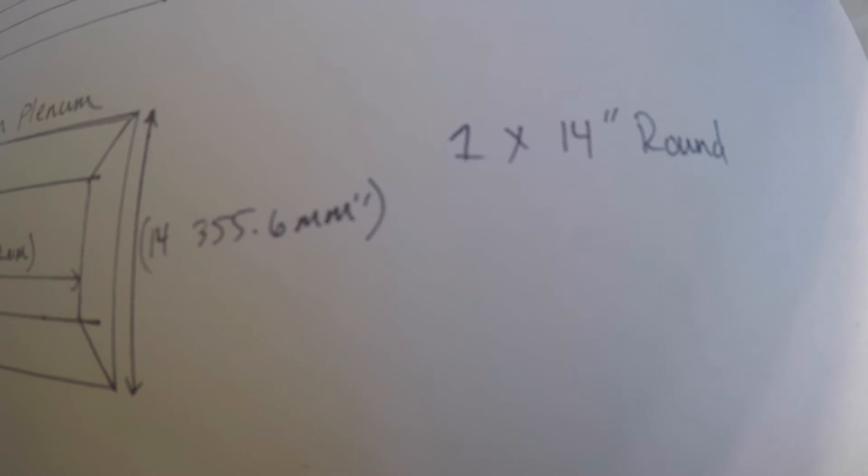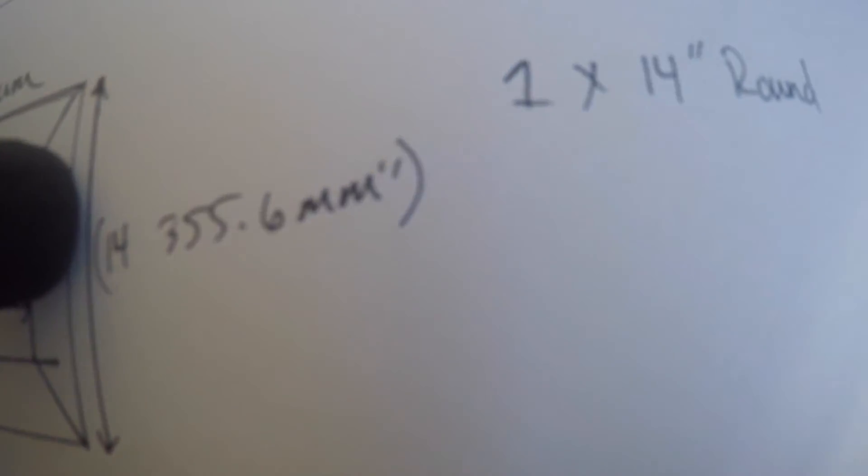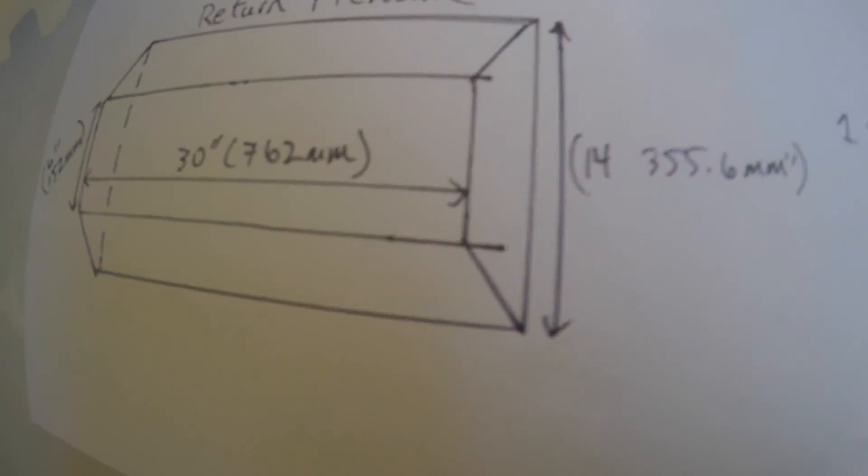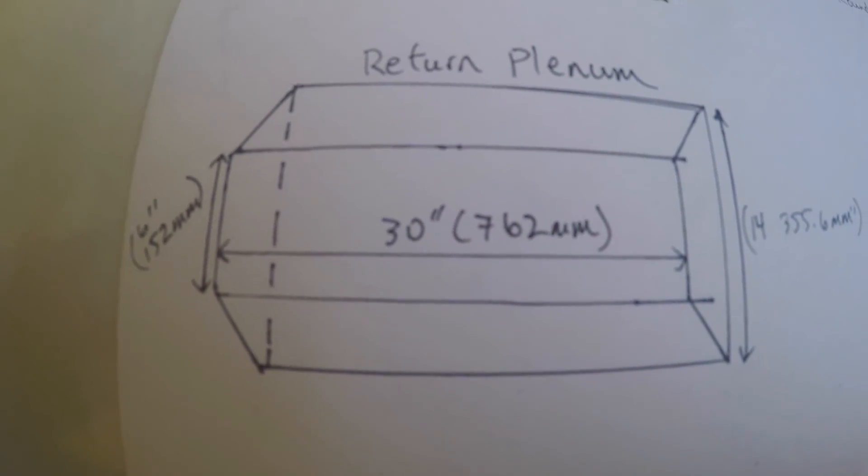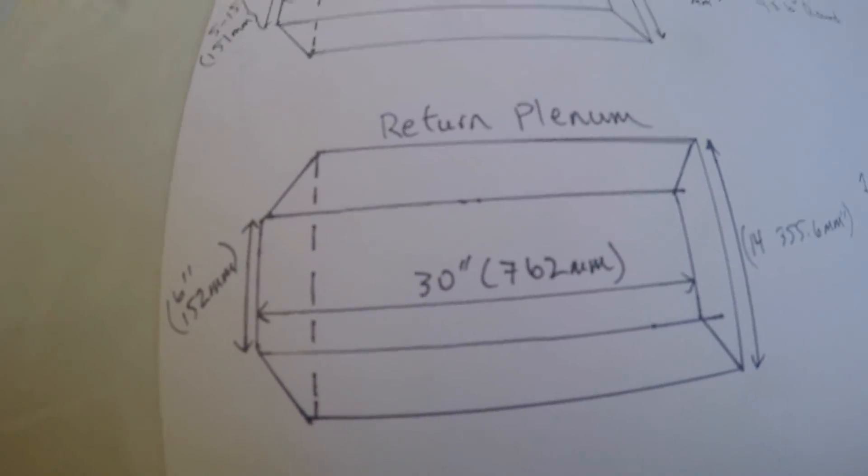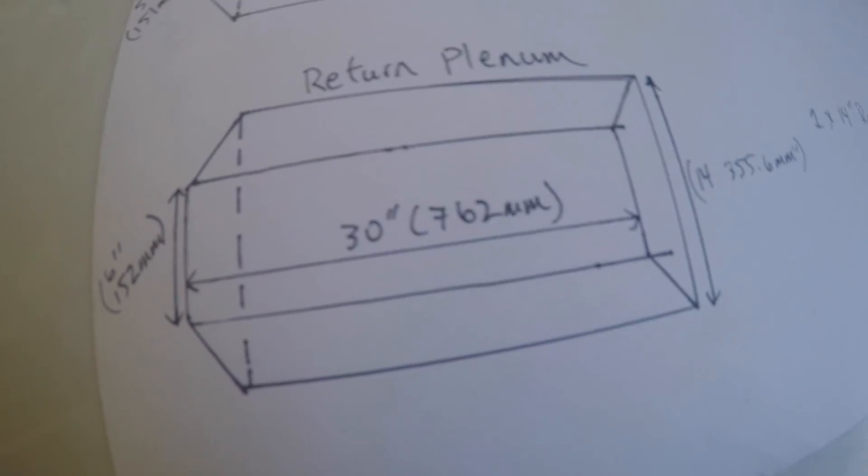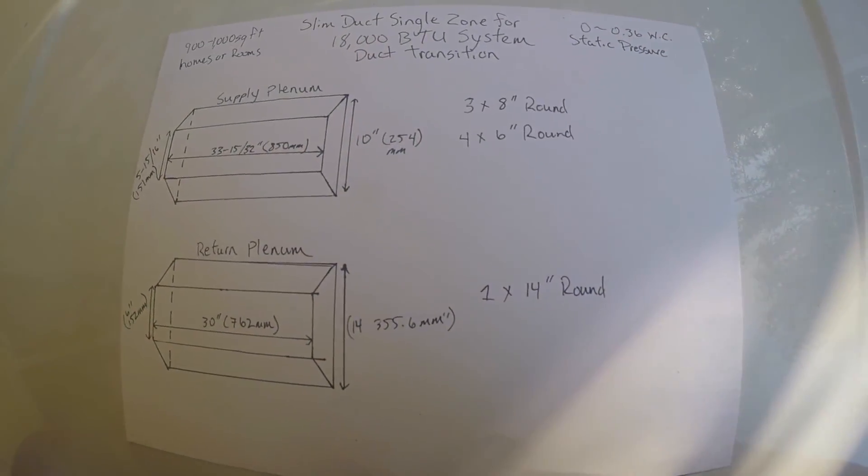would be around 14 inches. So it's up to you if you want to increase this a little bit, but I've been able to work that out pretty well with what we have here. Through measurements and through superheat, subcooling measurements, and everything like that, static pressures - these are kind of what we're looking at based on the information.